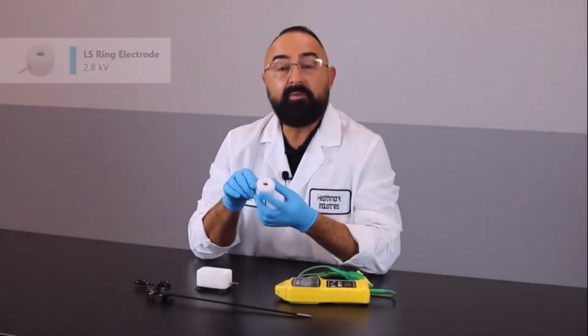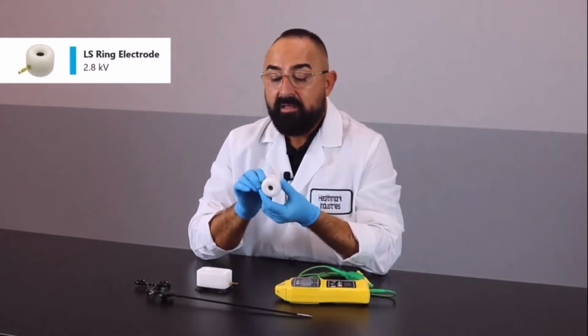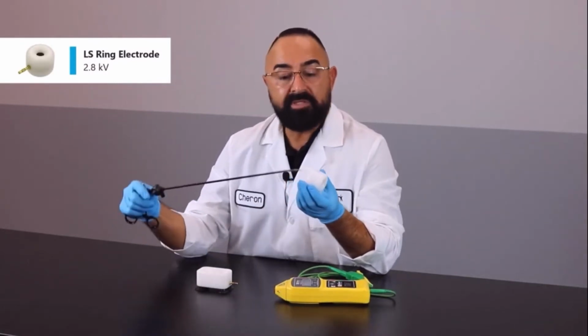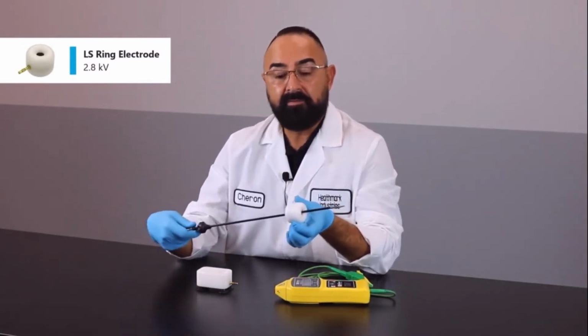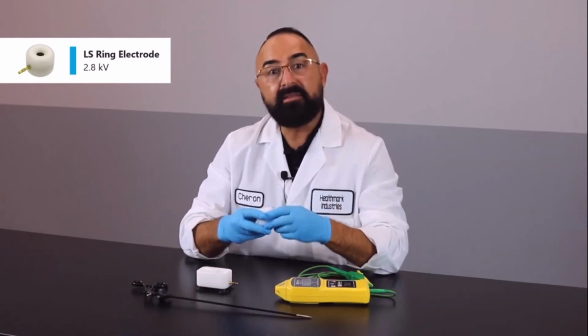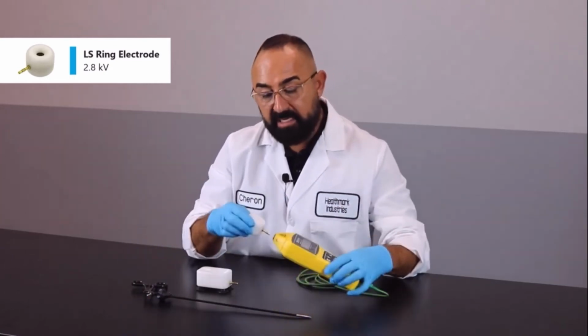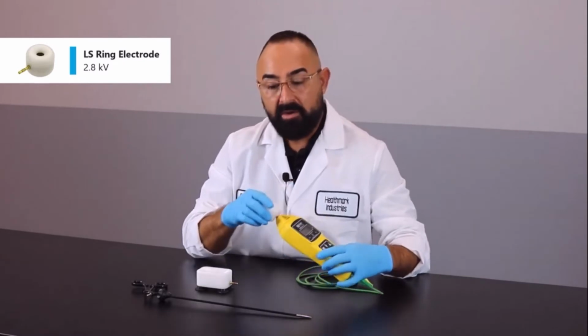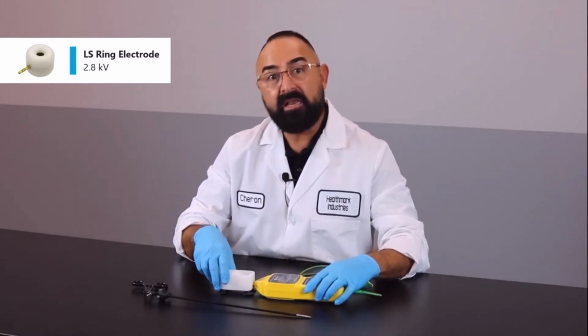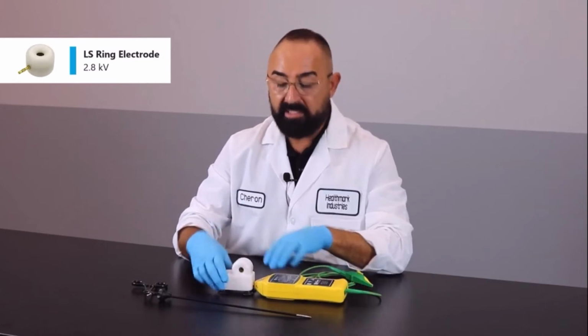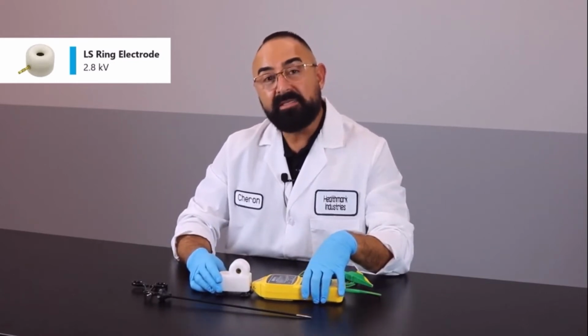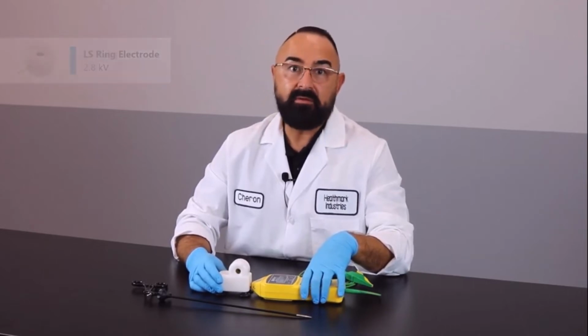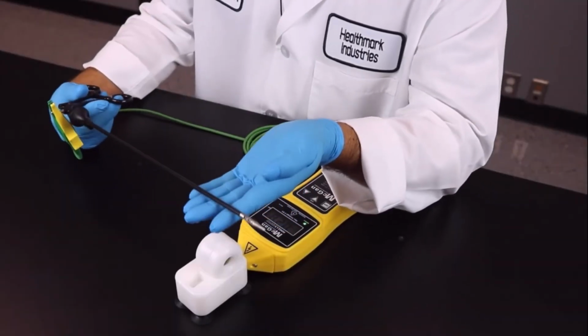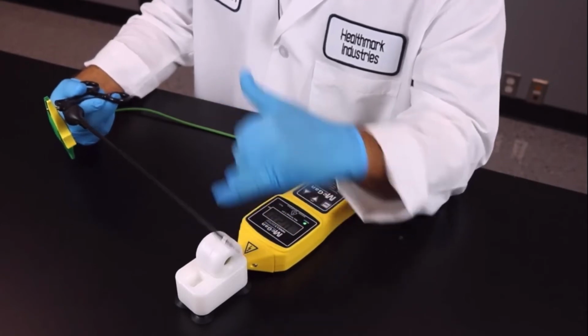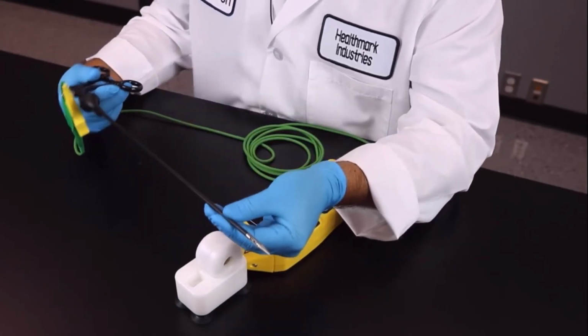The first accessory that we're going to address is called the LS ring. The LS ring is used for laparoscopic instrumentation like you see here. There's two ways that you can actually set this up. The LS ring accessory can attach right to the base unit, or ideally to the saddle block, for two different reasons. One, it's less cumbersome when you're testing, and for safety reasons as well. A good laparoscopic instrument will not alarm between distal and proximal end of the insulated shaft.